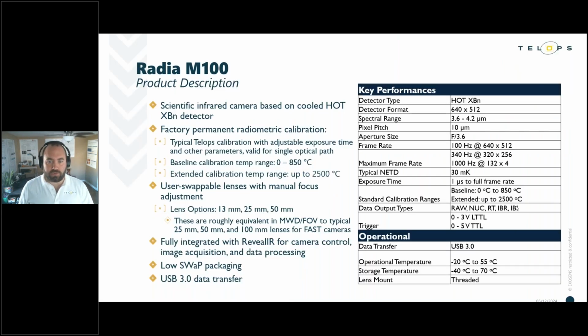All right, so this slide shows the main specs of the Radia M100. We have a 640 by 512 XBn detector array, which has a 10 micron pixel pitch and is sensitive over this 3.6 to 4.2 micron midwave spectral band. So it's a smaller spectral band than the traditional midwave 3 to 5 band, but this does allow us to offer this baseline calibration from 0 to 850C.